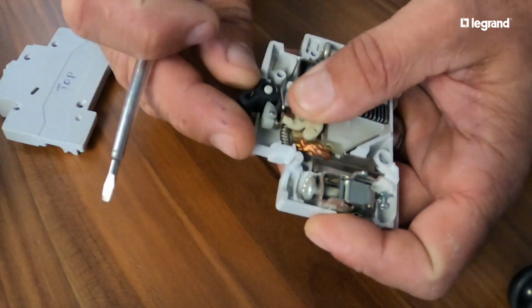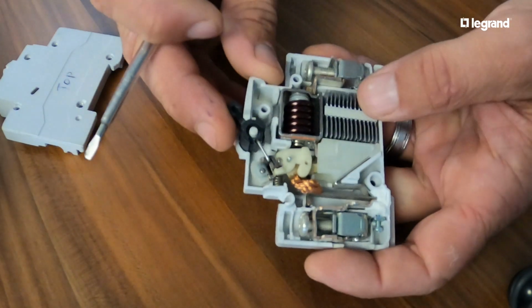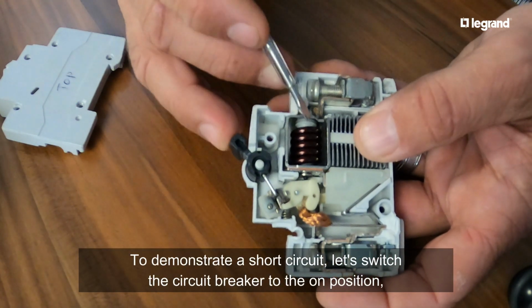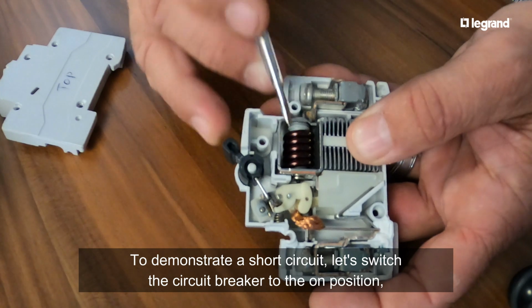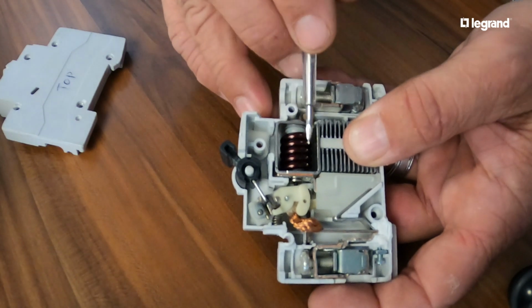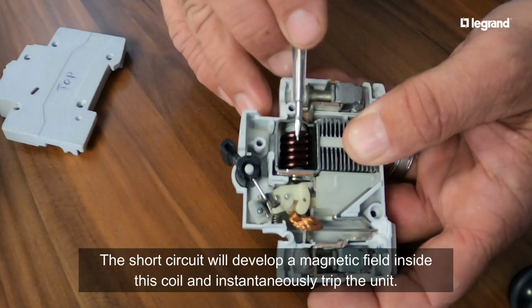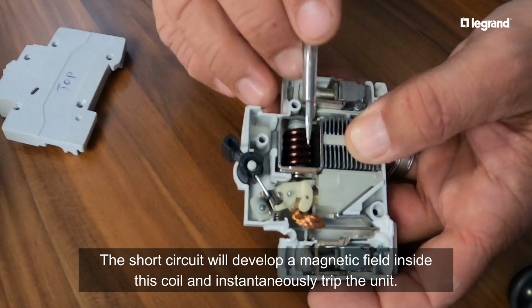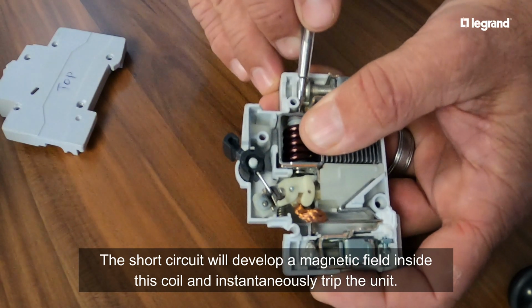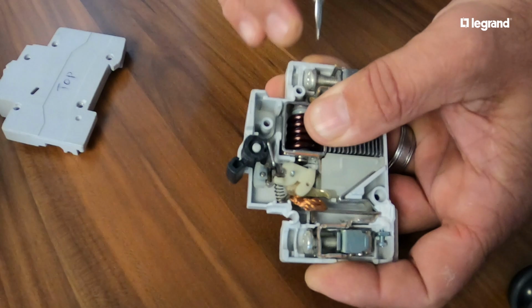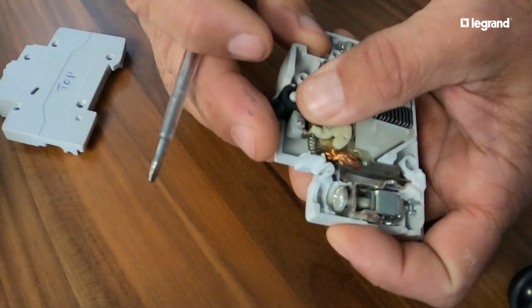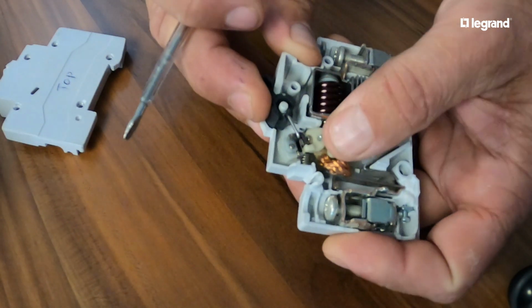So I'm going to switch the circuit breaker to the on position. Now I'm going to illustrate a short circuit. The short circuit is going to develop a magnetic field inside this coil, instantaneously tripping the unit. So the plunger goes down and it trips the circuit breaker. That's a good illustration of a short circuit.